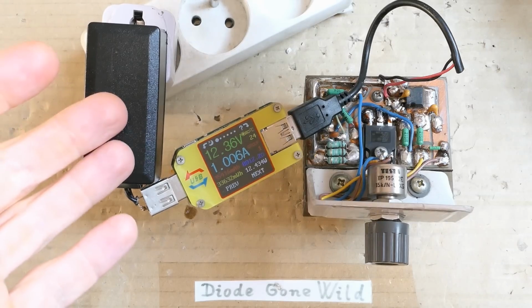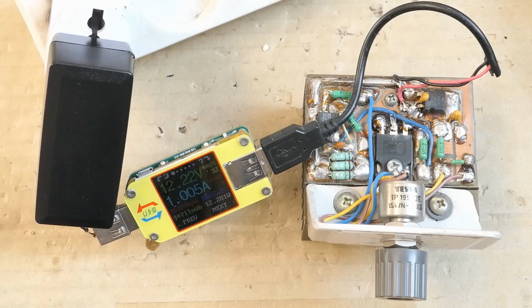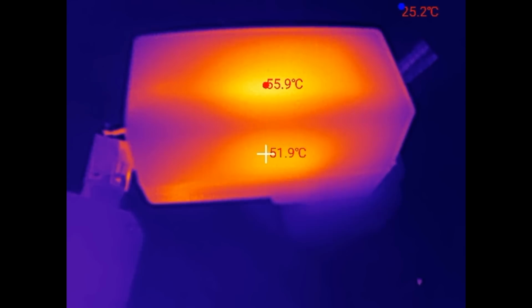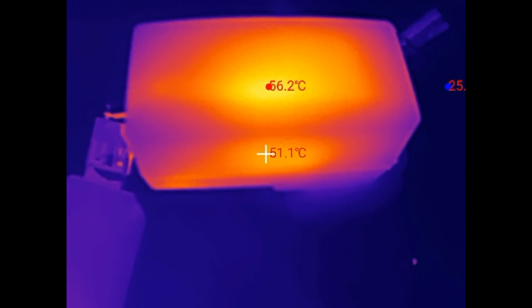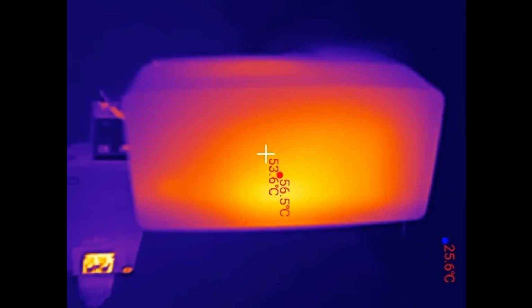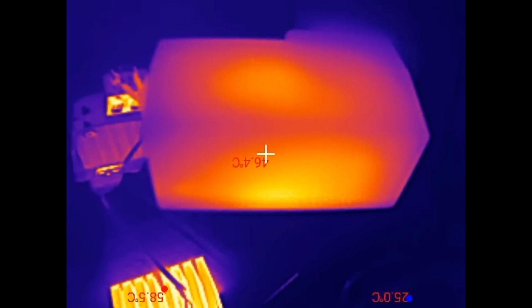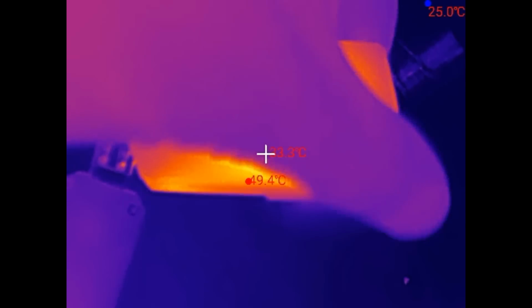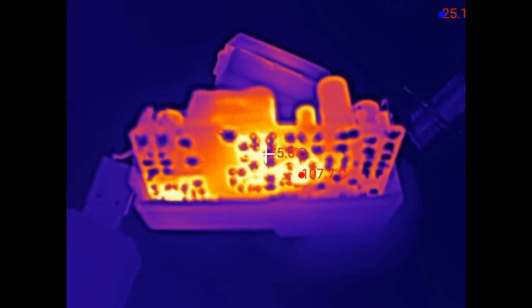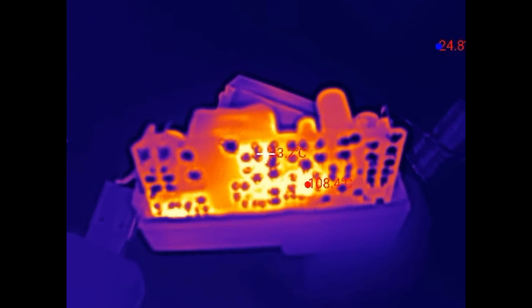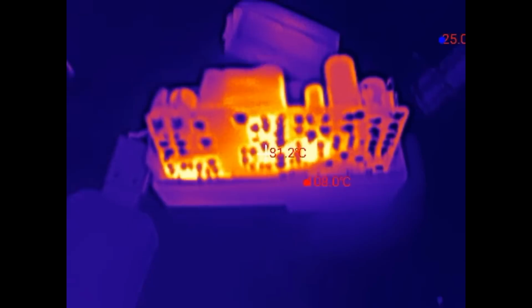I've put the cover back on, let's leave it running for a bit longer. After 2 hours, no failure. Some quick thermal imaging from the outside shows about 56 degrees, nothing bad. Taking the cover off, about 107 degrees Celsius at the hottest part, which is the chip, and the board under the chip. The transformer is about 87 degrees.